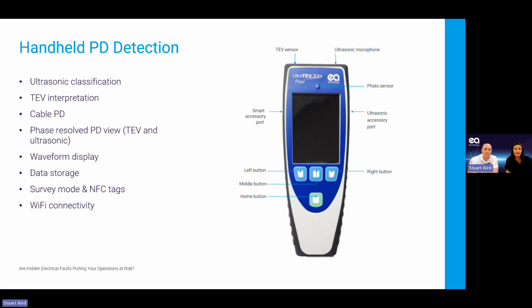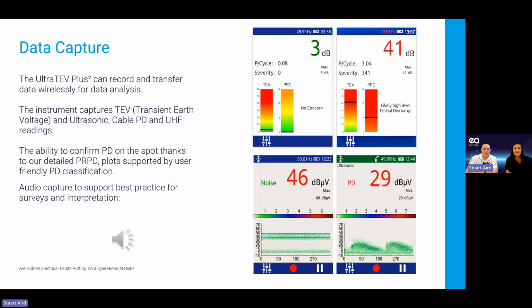Moving on to what data it captures. A key advantage of the UltraTEV Plus 2 is the ability to verify and assess the partial discharge activity immediately. You get phase resolved partial discharge plots, which are available on the instrument, helping to distinguish between different PD sources, and you'll see that on the screen. This is what you will hear when you're listening in through the ultrasonic on the partial discharge. You'll hear that crackling noise, and that's what you'll be listening out for.